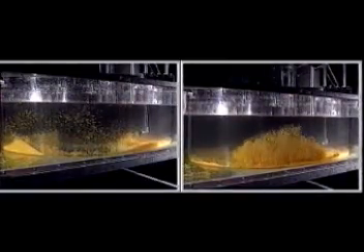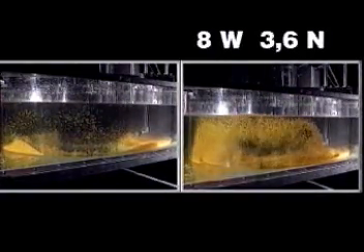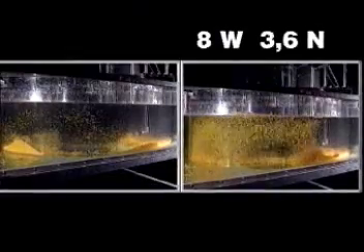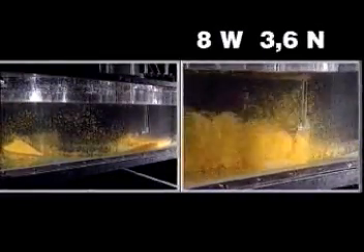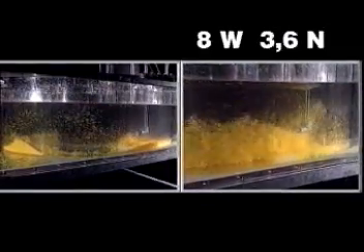Now notice the difference in the right picture. The energy from this jet is translated into a bulk flow throughout the tank rather than just in the vicinity of the propeller, and the particles are well suspended by the bulk flow.